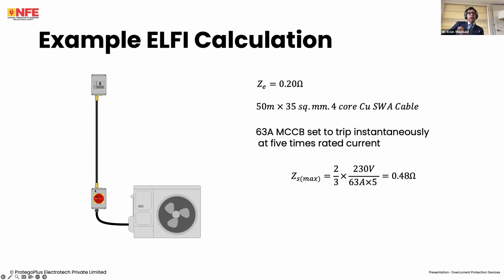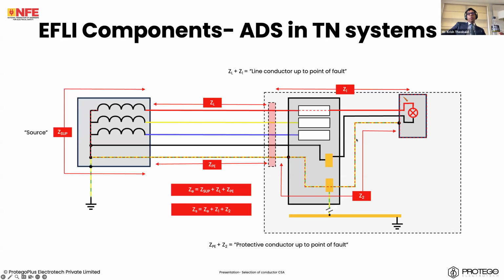I have an MCCB, I have an isolator, and I have a load, an air conditioner, a three-phase circuit. I'm using a steel wire armored cable. Okay. I have glanded at both ends as I should. And the armor is my protective earth conductor. Now, there are two practices in the industry. Practice number one is that the armor is used as the protective earth conductor. Practice number two, the armor is used in conjunction with a parallel conductor as well. In this case, the armor is also part of your Z2 value. Now, not only do I have to consider the effect of the armor, I also have to consider that there is a certain inductance, there is a reactive component to it.